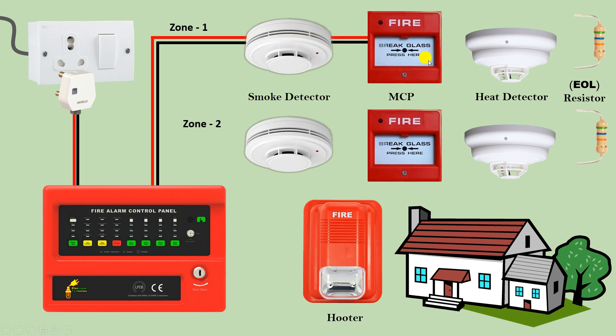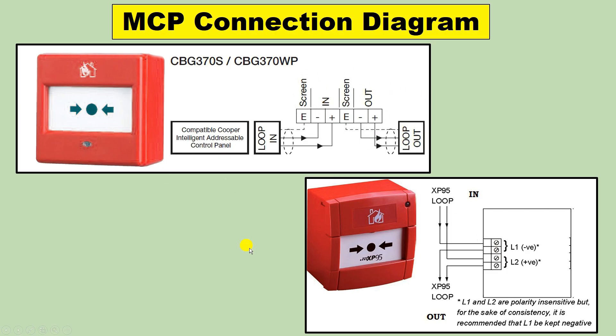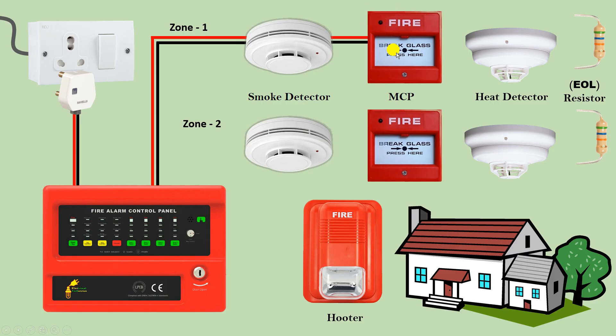After this, take the power supply from the previous detector and do the connection of the MCP. Behind the MCP the terminals work similarly — connect incoming negative to the negative terminal and loop outgoing negative to the next device; do the same for positive. Details are labeled on the terminals. So connection of the MCP is done.